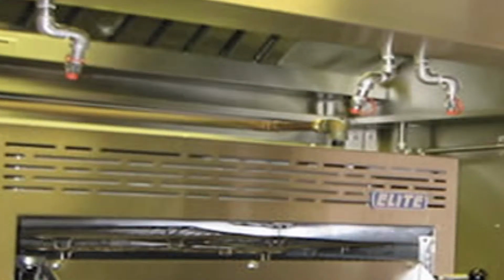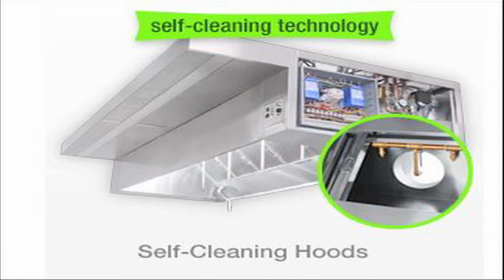It cannot be obstructed. The nozzles must be free and clear, and the cooking equipment design must remain the same as original. Ultimately, we need to prevent the accumulation of grease. Grease is the cause of the fire. First, we should change our filters on a daily basis. We should do duct cleans anywhere from once a month to every 3 months.